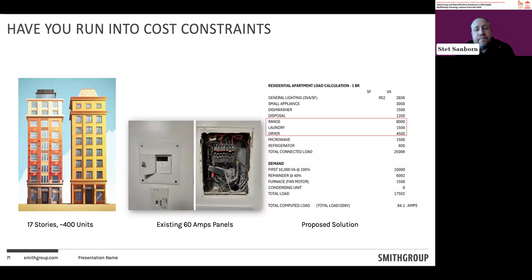But what they wanted to do at these apartments, besides just the HVAC, is electrify the whole building to get off of gas completely. So they were going to swap out the gas range, swap out the gas dryer, and the central laundry. They had in-unit laundry, but they also had some shared laundry uses. When they added up all that new load going into the apartment, the load count jumped up to about 84 amps. So not enough capacity on that 60 amp panel. That was the assessment done by the team that was brought in to take a look at it. Next slide.